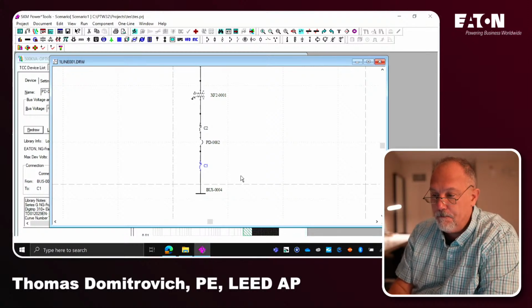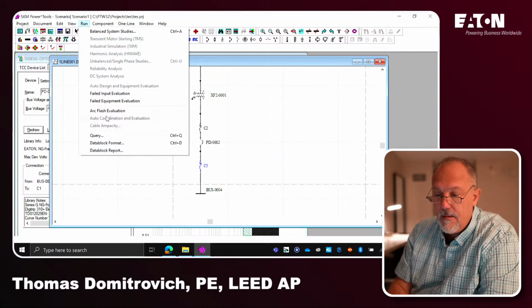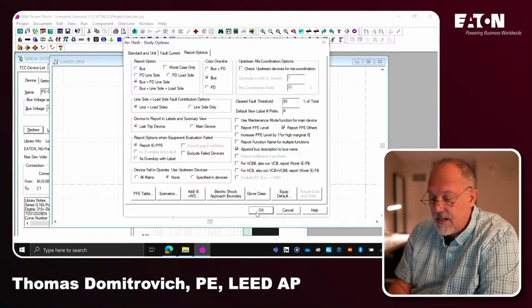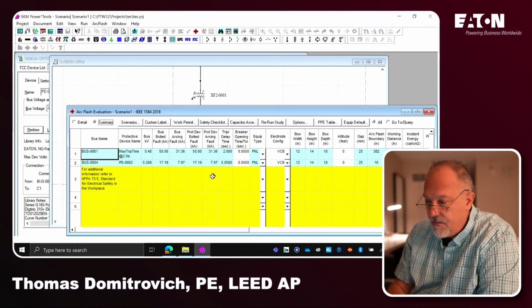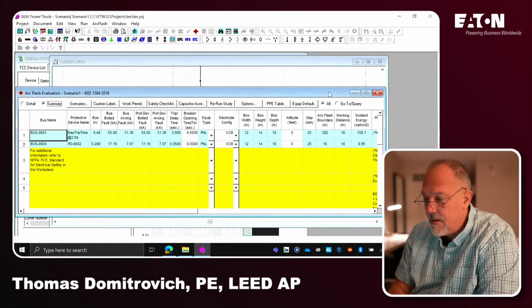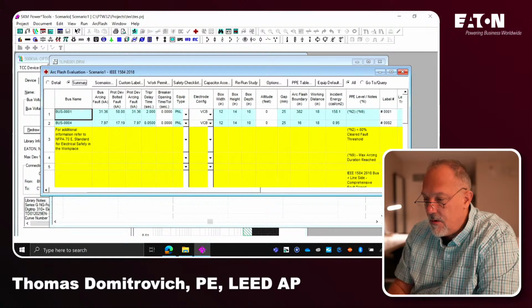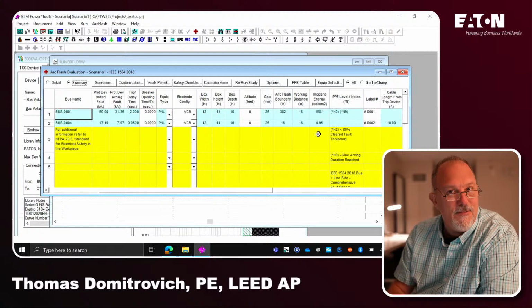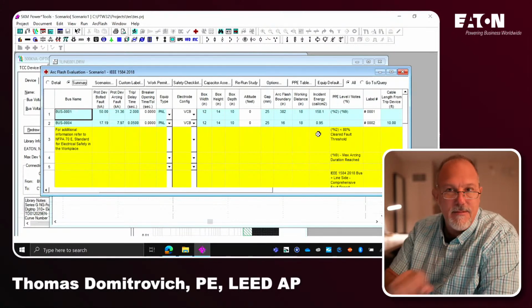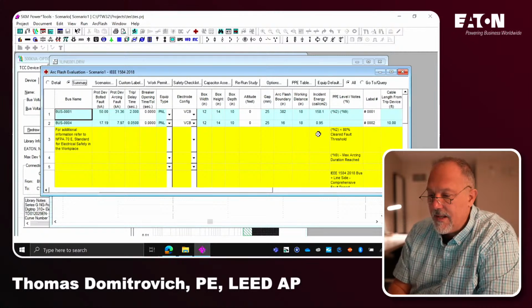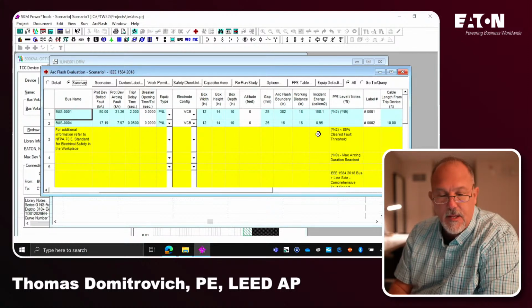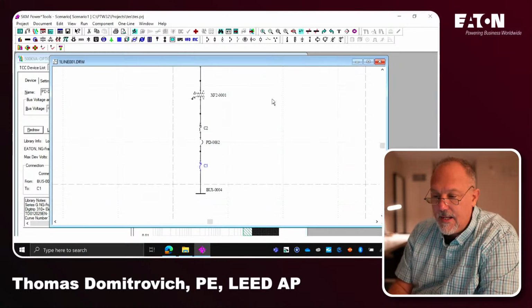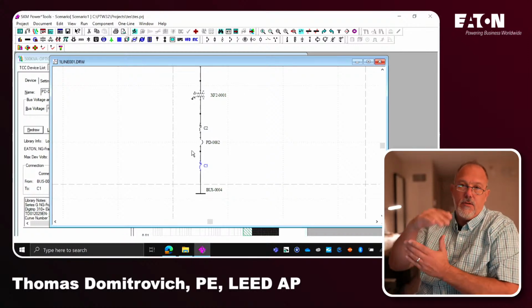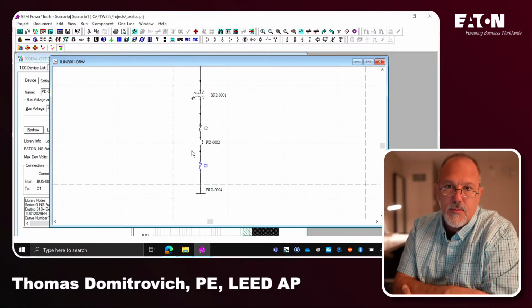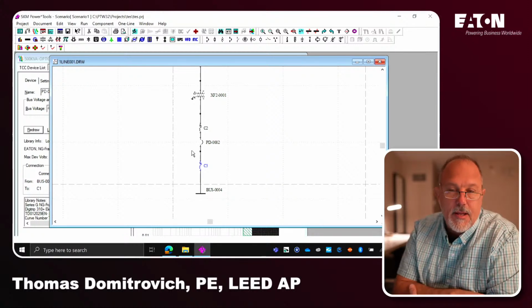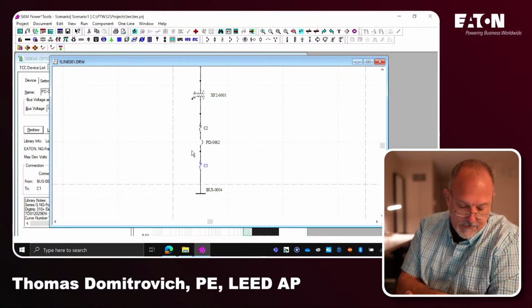All right, so now I'm going to run my arc flash evaluation. All of the same settings. I hit OK, and bus 4 incident energy is 0.95. Tell me that is not sweet. So my incident energy went from 33 something to 0.95, and all we did was move that 2000 amp breaker into its own disconnect, feeding a main lug only switchboard or panel board. In this case, it was a panel board, power line 4, 2000 amp. So that's all we did.